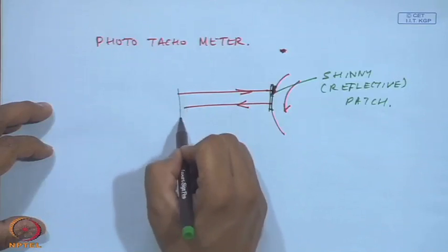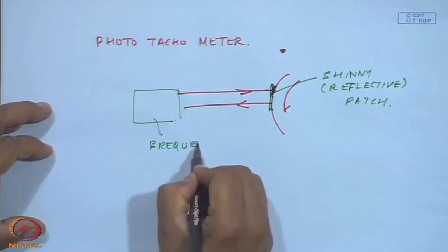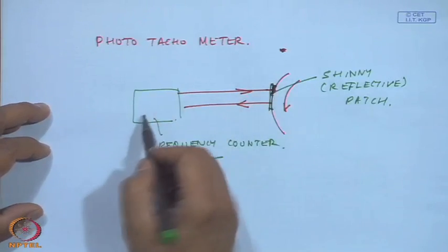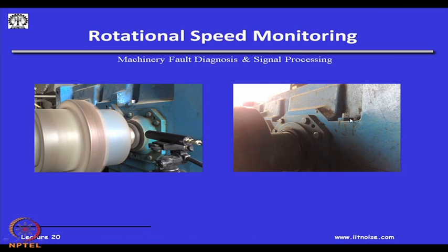And then you can have a frequency counter, and then we can measure the rotational speed, or you can record it as well. And this is out of a gearbox. You can see a shiny white aluminum block, actually. It is an aluminum block wherein this is the casing of the gearbox. It is not possible to tap it at this side. So, all we did was put a mounting block and glue it with a cement.